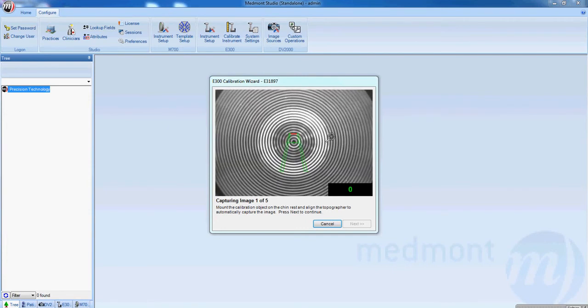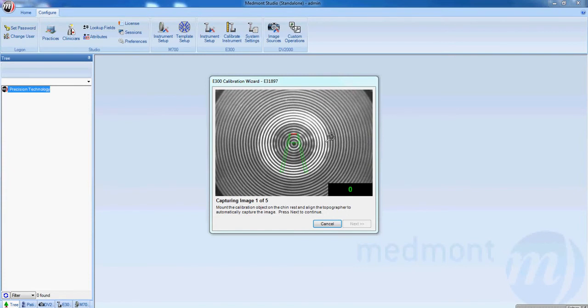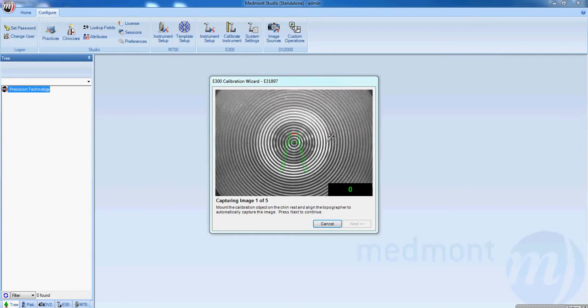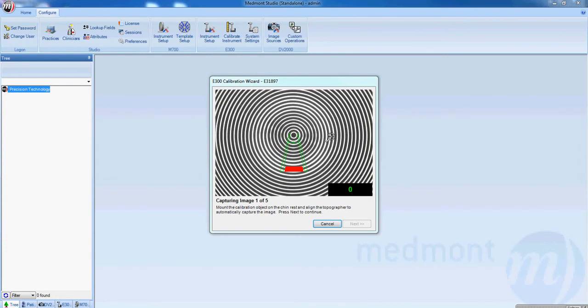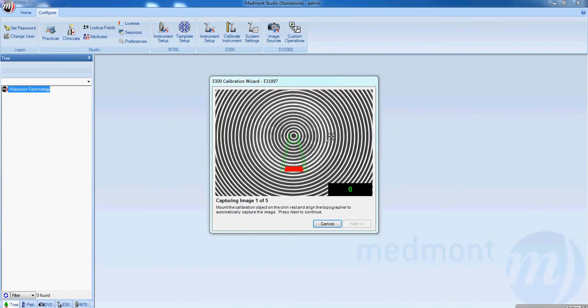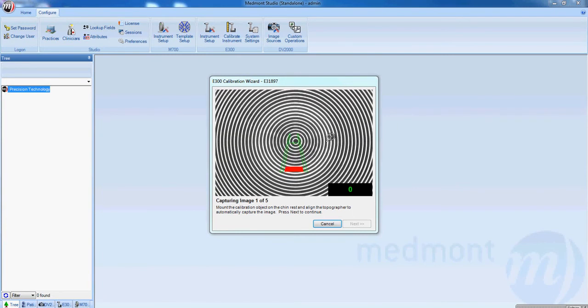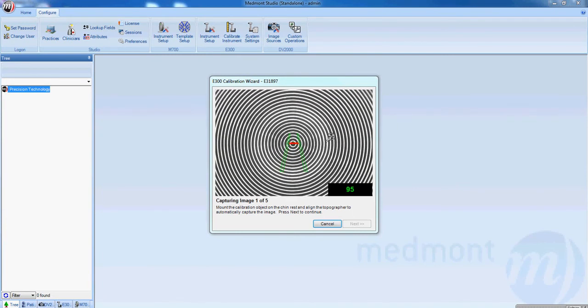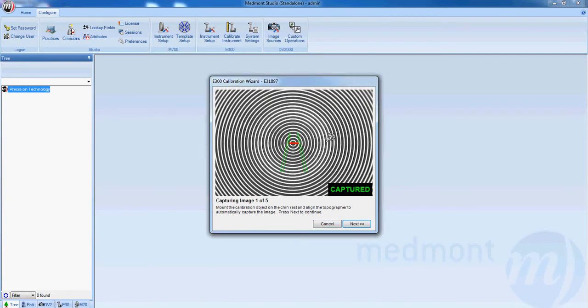Then look at that red distance indicator at the top of the runway. While the red line is at the top of the runway, the instrument is too far away from the calibration ball. While the red line is at the bottom of the runway, the instrument is too close to the calibration ball. Line up the green crosshair and the red distance indicator over the apex ring. The software will automatically capture when the instrument is in the right position.